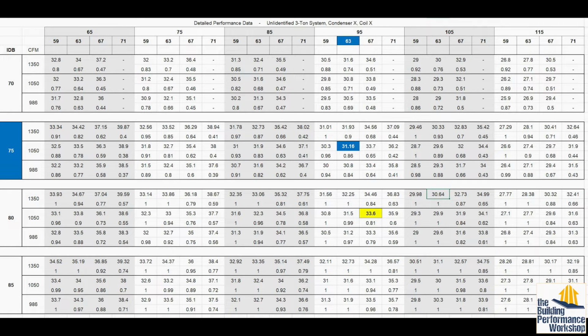80 degrees in the return. You have got to be kidding me. 80 degrees in the return is not normal conditions. Okay, 80 degrees in return is like something is wrong. Now, you bring in some outside air and get a little bit of duct leakage. The temperature may not be exactly 75, but to get it all the way up to 80, that's crazy.